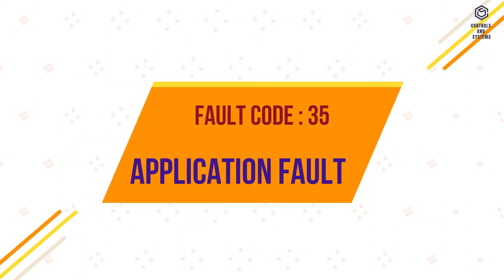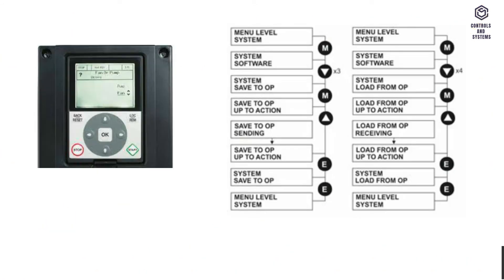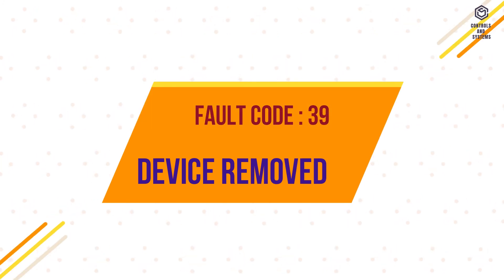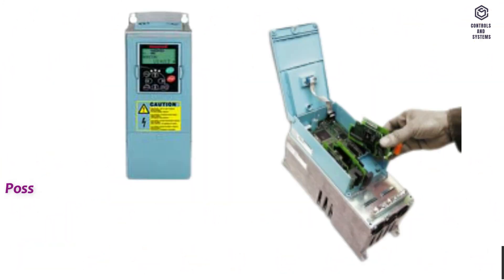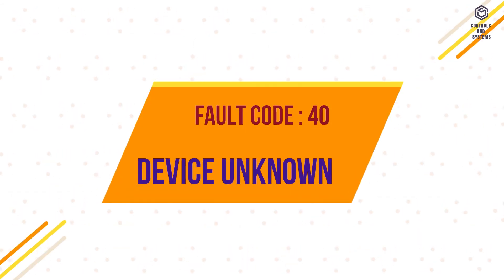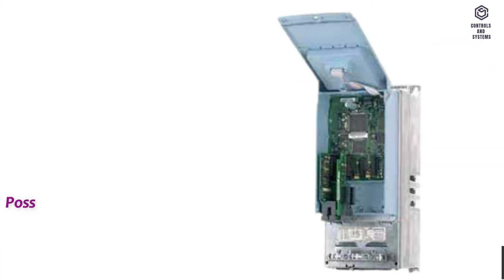Fault code 35 – Application fault. Possible cause: the selected application does not function. Remedy: contact technical support. Fault code 39 – Device removed. Possible cause: option board or drive has been removed. Remedy: reset the VFD drive. Fault code 40 – Device unknown. Possible cause: unknown option board or drive.